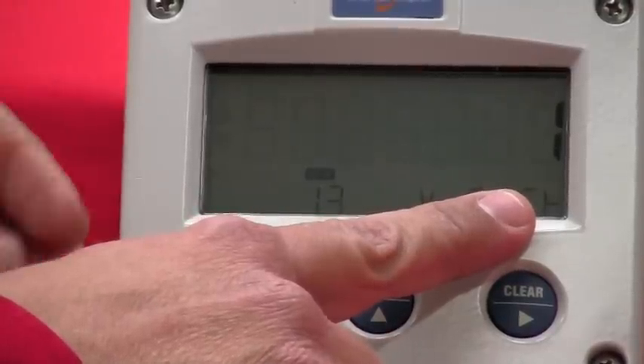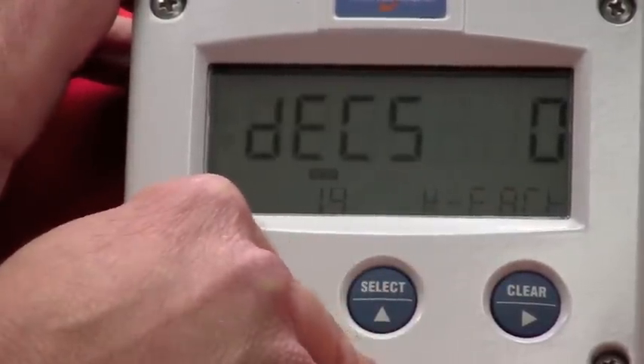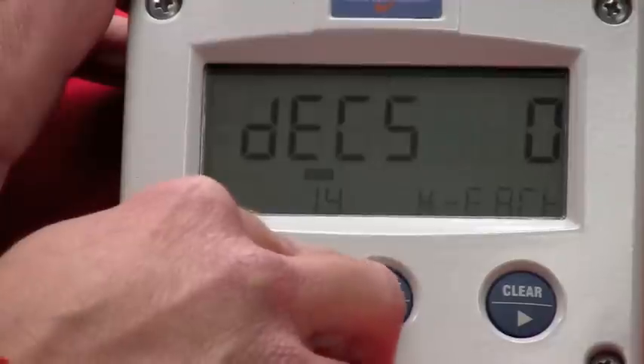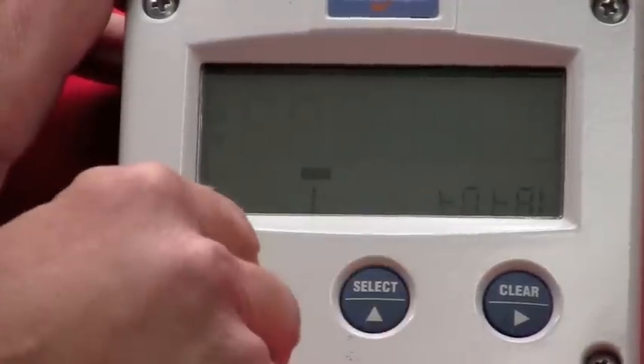The K factor right now is set for one. For an effective demo, you want to leave this at one. That way every pulse that you're generating with the little switch is going to register as a count of one. Next up is the decimal points for your K factor. Hit it again. You're back to the top of the menu.